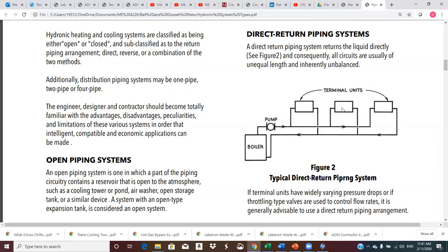If I look at the furthest unit, here's the common piping to here. We split off some here, the rest of it goes down, we split off some more here, and then the rest of it has to go all the way down here, so it has the longest supply path, and guess what? It also has the longest return path all the way back. So as far as pumping head is concerned, if the flows are equal, it's going to take much more pumping pressure to force the same flow rate from this point all the way down to here, through the coil and all the way back, as compared to the other 2 circuits. But so short down, short back, long down, long back, that's a characteristic of a direct return system.